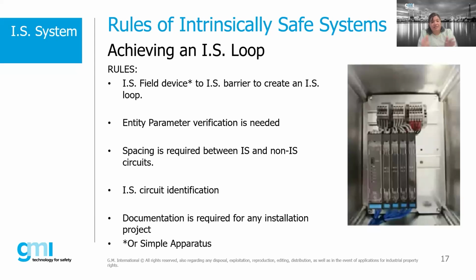There has to be space and separation between intrinsic safety and non-intrinsically safe items and circuits. So IS wiring cannot touch non-IS wiring, and there are some rules - the distance is 2 inches for North America, 5 centimeters in the metric system, or 50 millimeters.